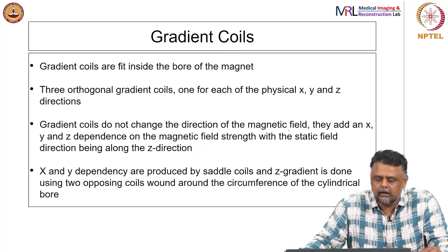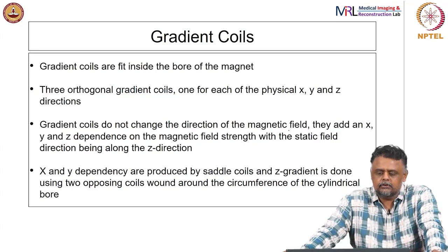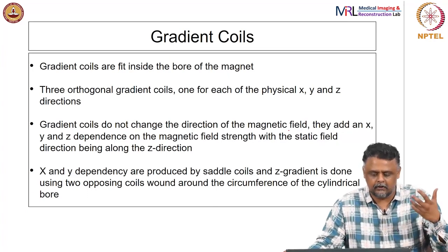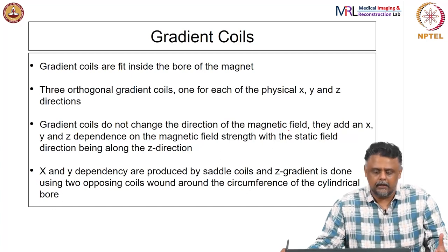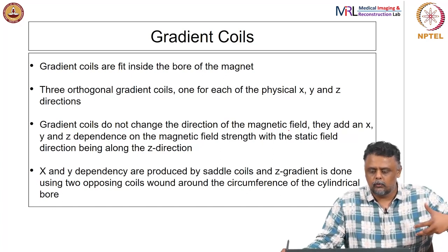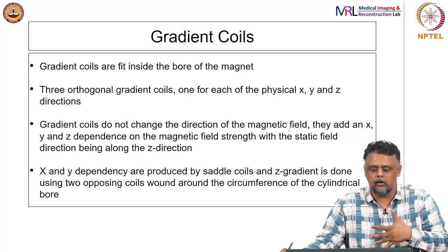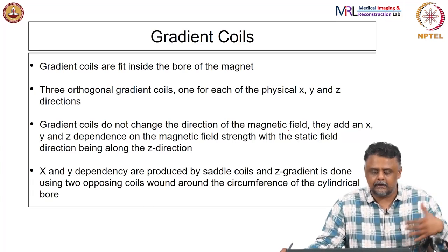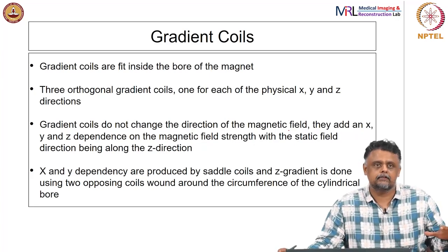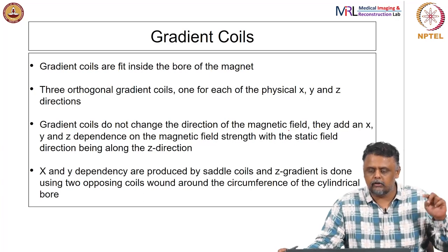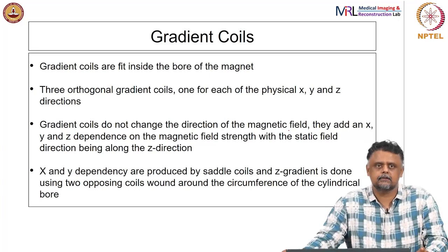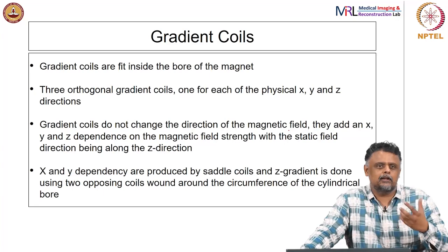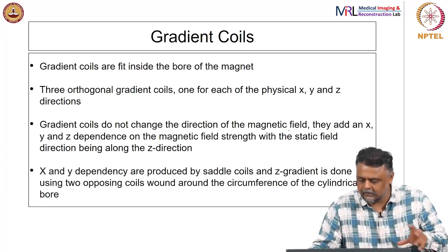The gradient coils are also basically current-carrying wires that give rise to magnetic fields. They are fitted inside the bore of the magnet. There are 3 coils, each orthogonal to the others, producing magnetic field gradients orthogonal to each other. The X and Y dependencies are produced by saddle coils and the Z gradient is done using two opposing coils wound around the circumference.